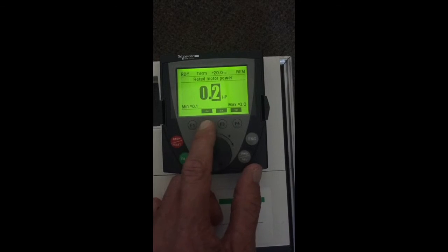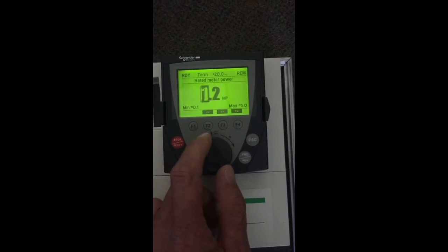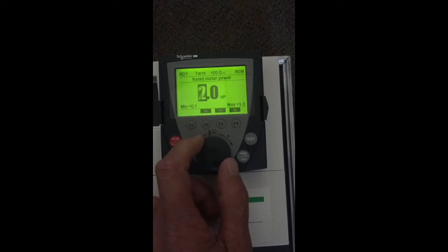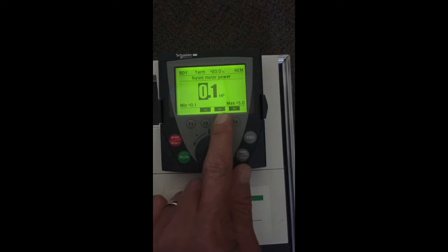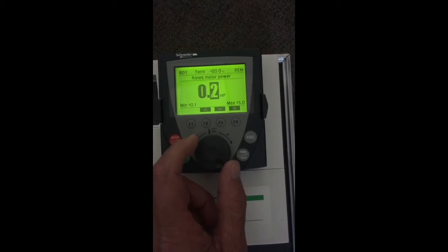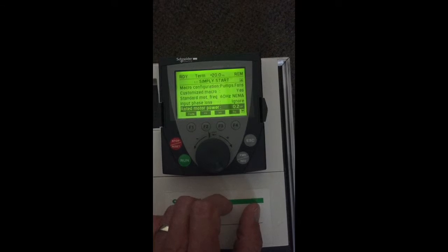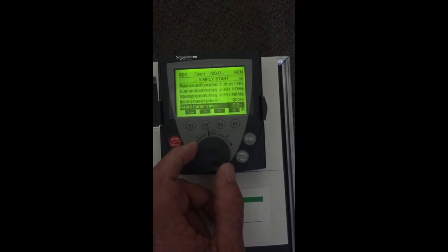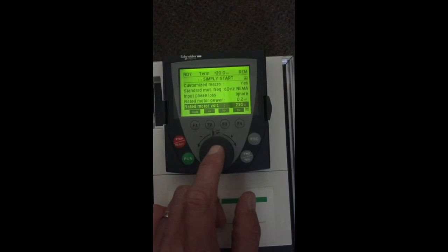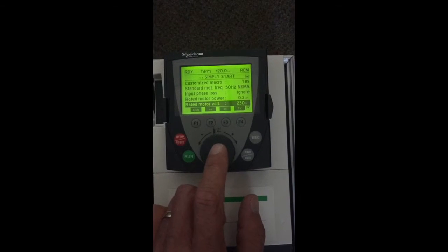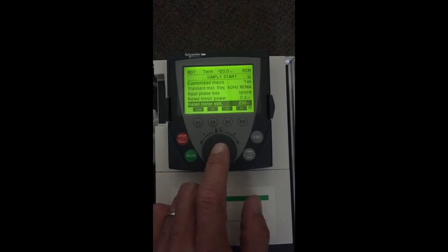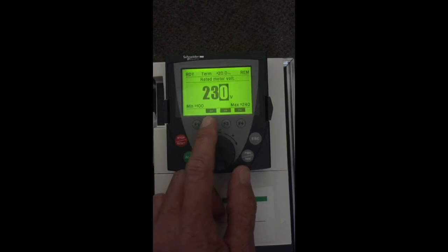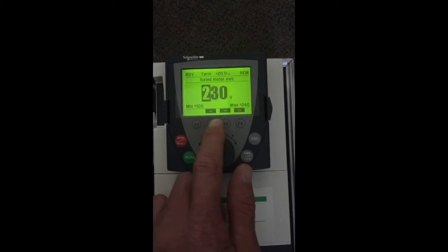You can move the cursor by the arrows to set up your horsepower. Enter in that information. Scroll down. Verify your voltage for your motor. If it's not correct, you can change that by simply going into that parameter and adjusting.